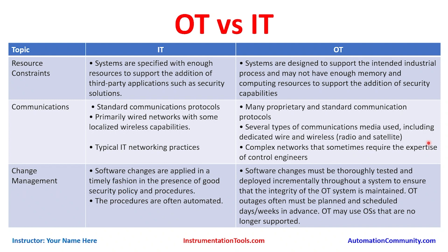OT networks are complex and sometimes require the expertise of control engineers. You'll find star topology in some parts of the plant, ring topology in others, and even mesh topology. For example, Foxboro DCS uses a mesh network at the field level — Level 1 — for high availability, and a star topology above that. Multi-topology arrangements change based on availability and redundancy requirements.